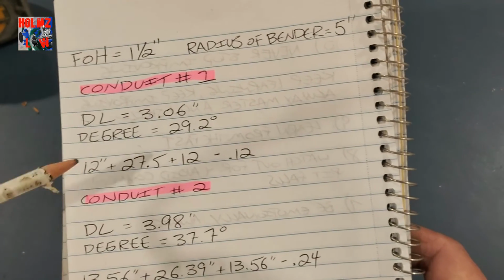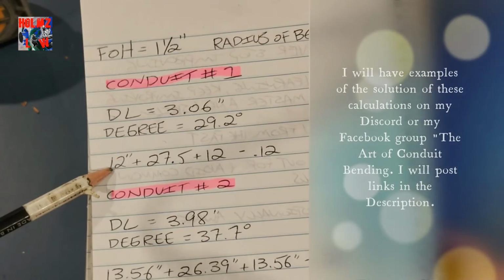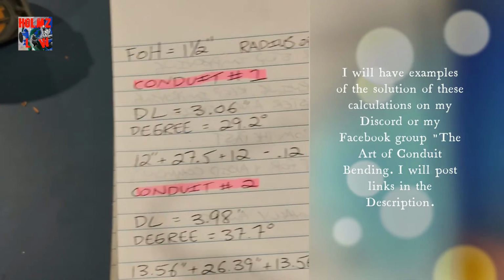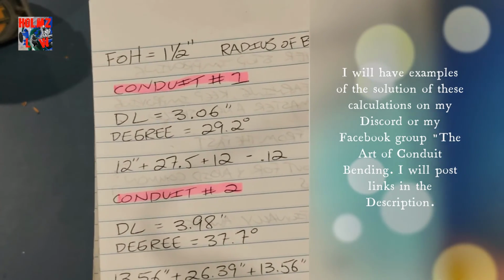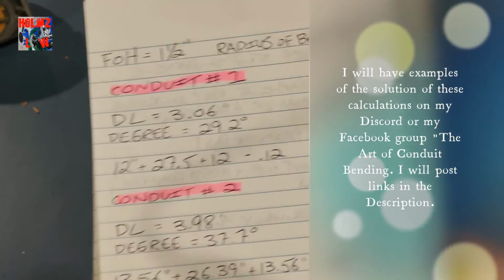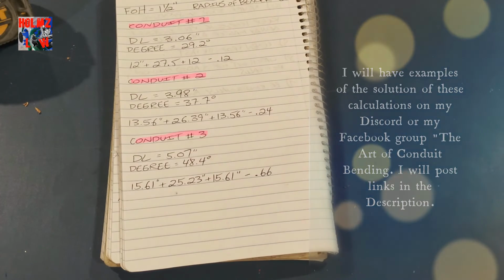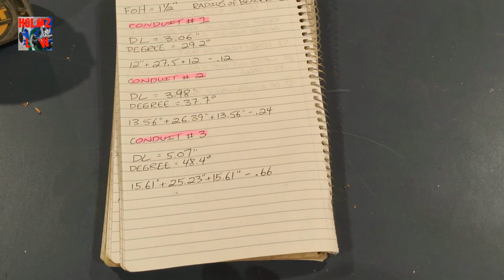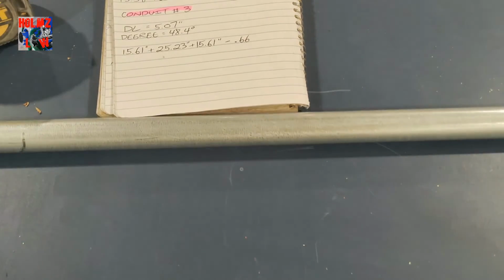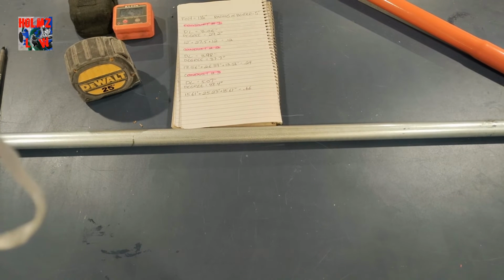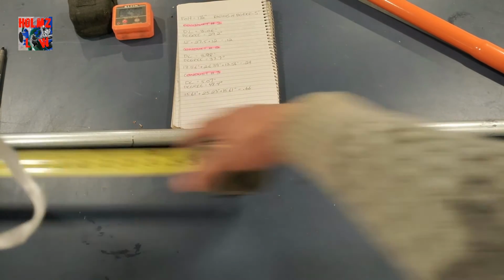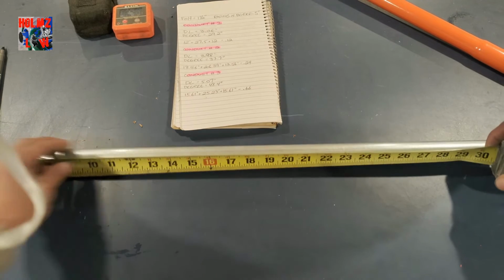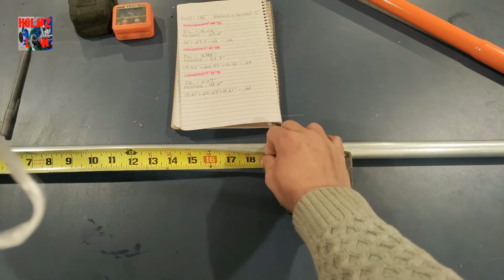So that I can actually explain this to you, 12 inches, this is our first measurement that we're going to measure from the edge of the conduit to the center of the first bend. And we're going to go ahead and mark that, and then we'll go to the second measurement, and I'll show you exactly how you can use this information to lay this out, okay? So our first measurement, as you can see, let me see if I can actually zoom out a little more. All right, our first measurement is 12 inches. We're gonna go ahead and measure those 12 inches, okay?